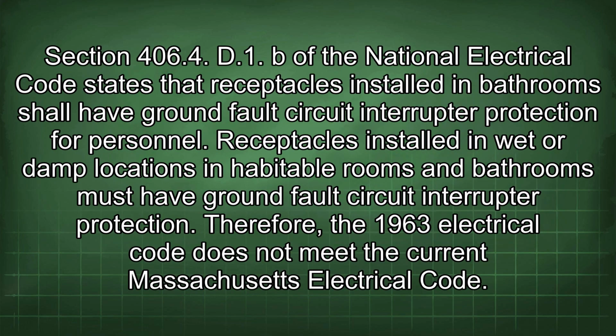Section 406.4(D)(1)(b) of the National Electrical Code states that receptacles installed in bathrooms shall have ground fault circuit interrupter protection for personnel. Receptacles installed in wet or damp locations in habitable rooms and bathrooms must have ground fault circuit interrupter protection. Therefore, the 1963 Electrical Code does not meet the current Massachusetts Electrical Code.